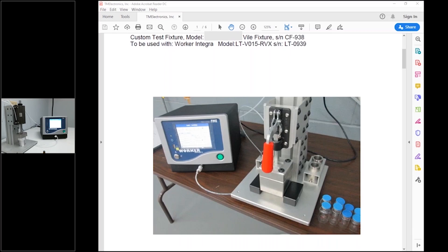When you do your leak test with that leak orifice, that leak orifice becomes your leak standard. You're always going to measure the same leak rate with that leak standard.